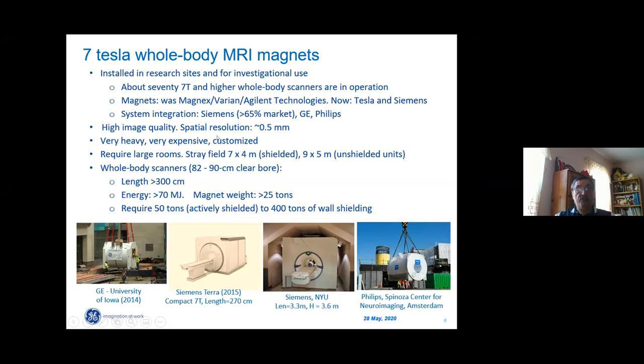But these magnets are very heavy, very expensive, with a very high stray field. So even in shielded magnets, the restricted access area is about 7 meters from the magnet. This requires additional very heavy iron shielding that may be on the order of 800 tons. That limits possible installation. The length of these systems is about 3 meters. Energy, over 70 megajoules. The weight of the magnet is over 25 tons.